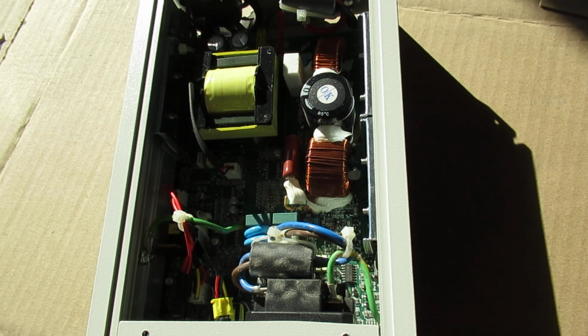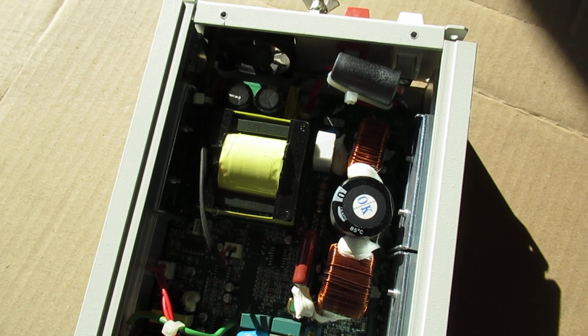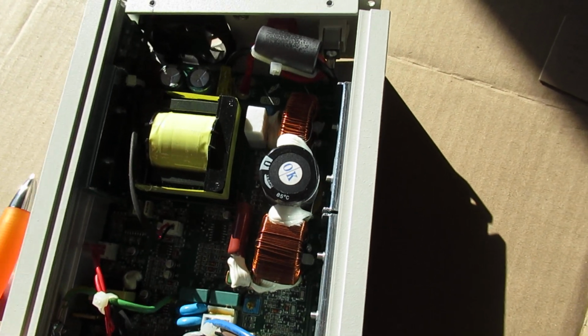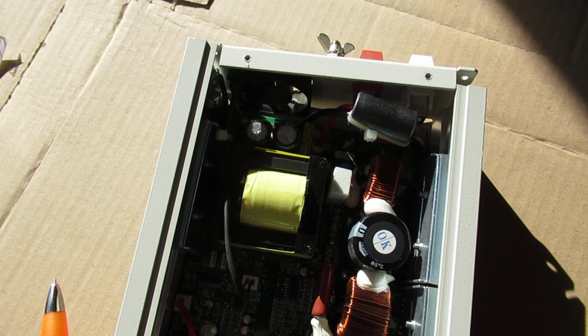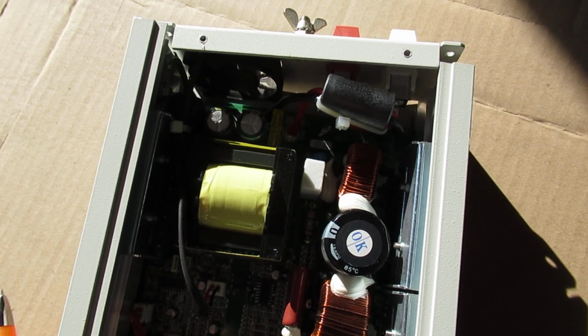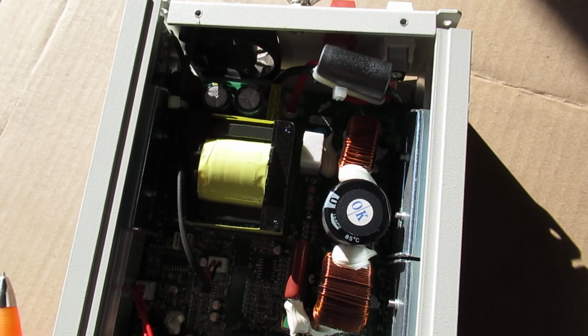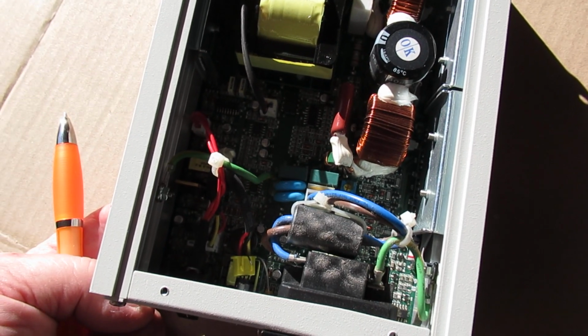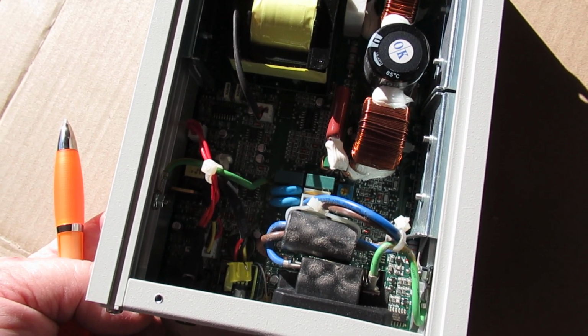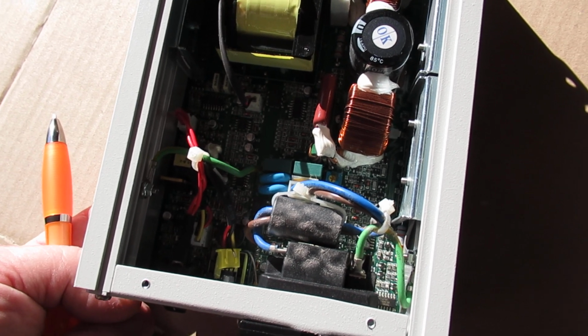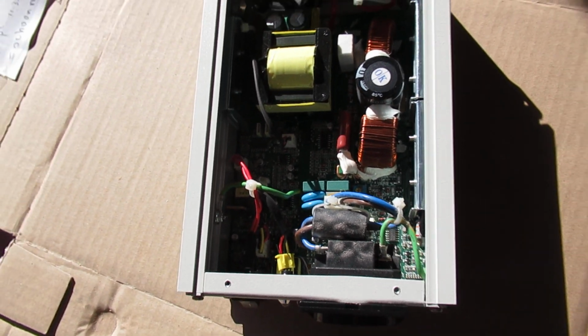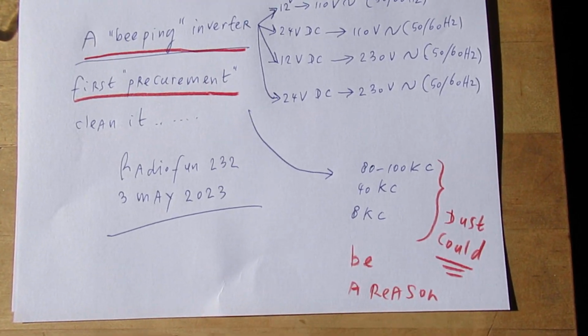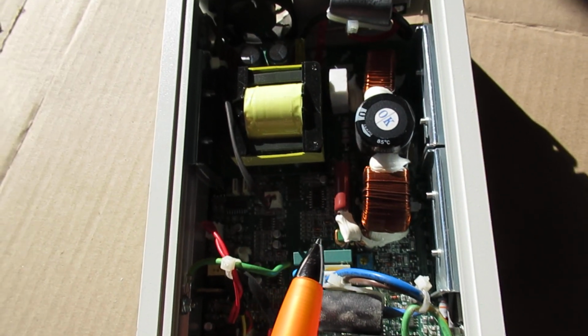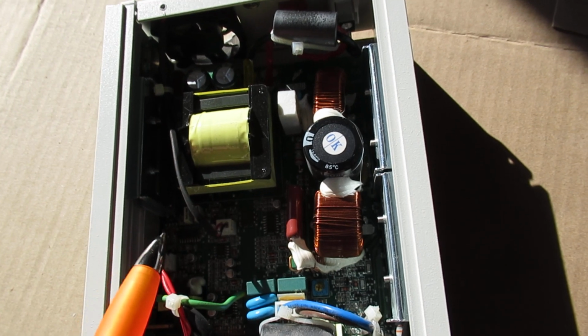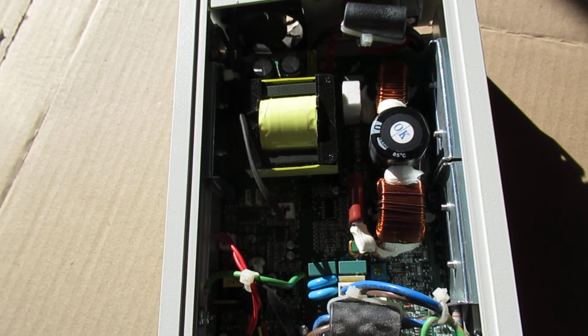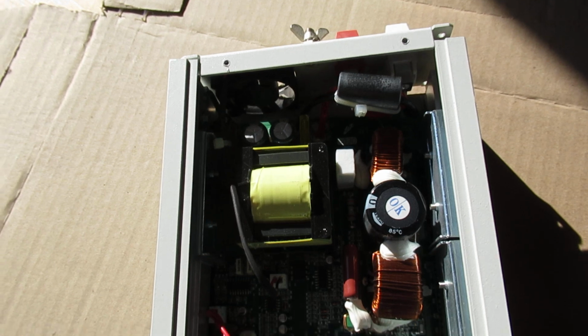This inverter works on a certain frequency where it transfers the high DC current to, say, modulated 230 volts or 110 volts AC. In general, such an inverter works in the order of 80 kilocycles up to approximately 150 kilocycles.